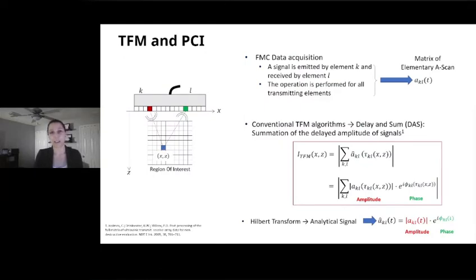So TFM and PCI now. PCI is also a technique based on FMC data acquisition. Here we're representing the same principle with element K and L to look at this pixel in the region of interest. TFM expresses it by looking at the amplitude of the signal for all the elementary A-scans. Using the Hilbert Transform, we can also look at the phase for that same signal. So we have the amplitude information, but we also have the phase information for all of those elementary A-scans in our FMC matrix.